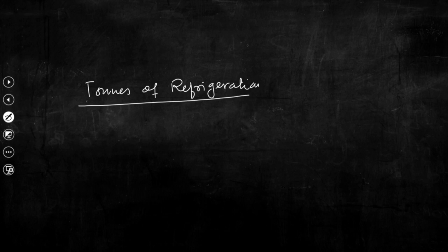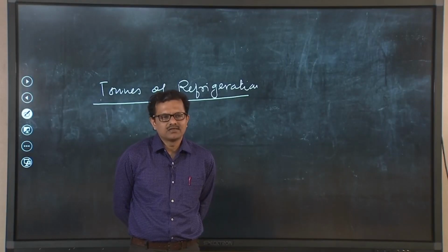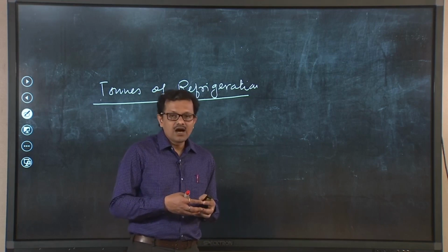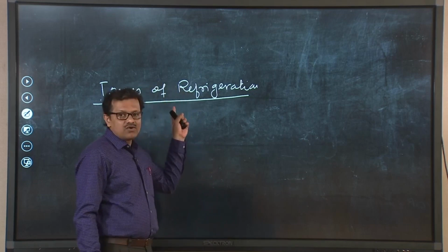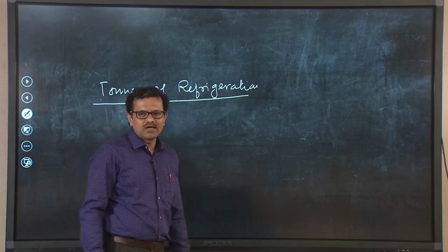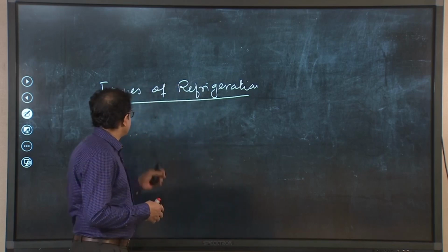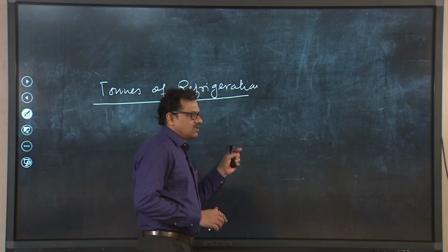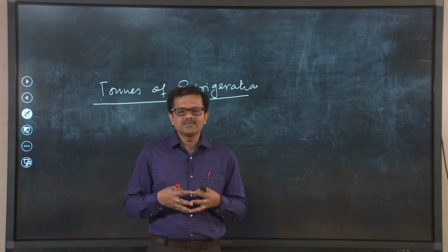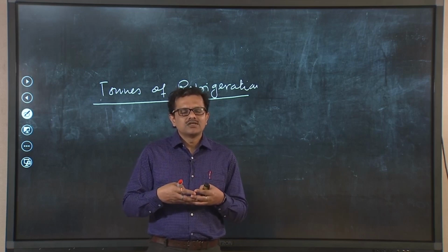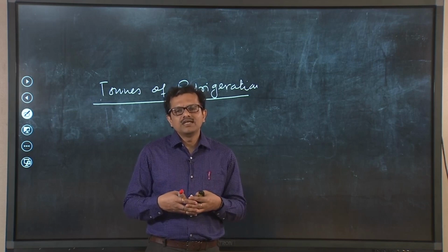and whenever a designer designs a refrigerating or refrigeration unit system, typically the most important term that is taken into account is the tons of refrigeration. So, this is basically the capacity of that particular unit, capacity of having refrigerating effect. So, what is the physical meaning of this? This is basically equivalent heat extraction that could change 1 ton of water into 1 ton of ice in 24 hours.